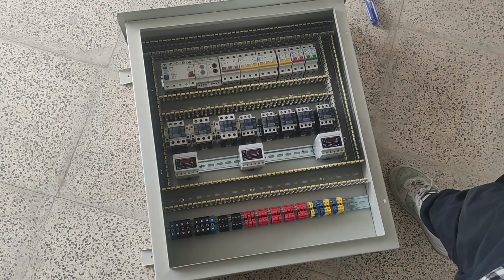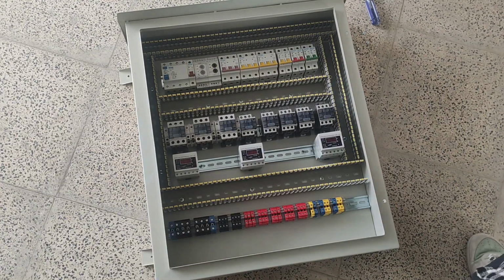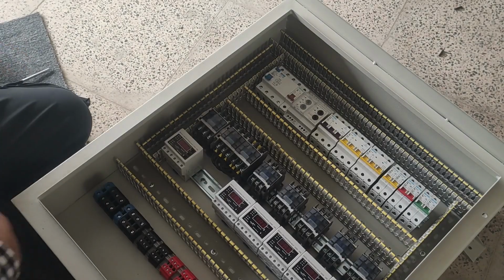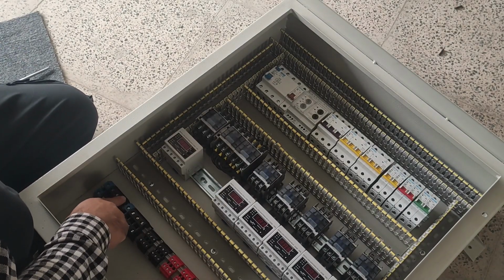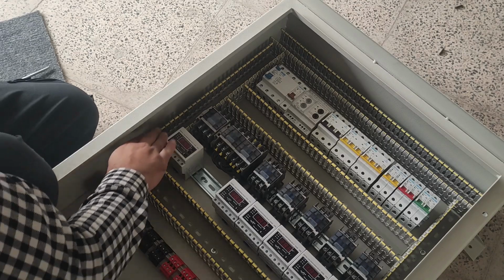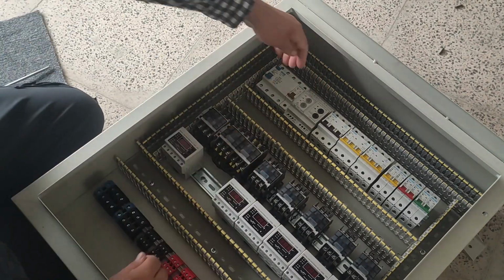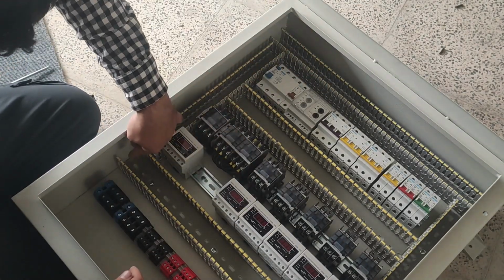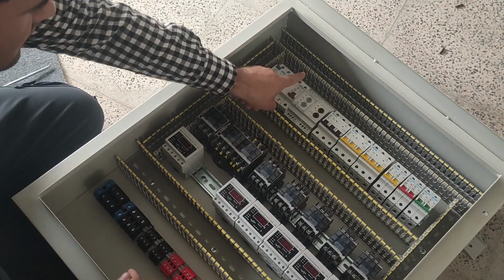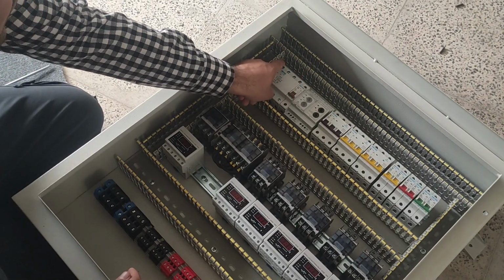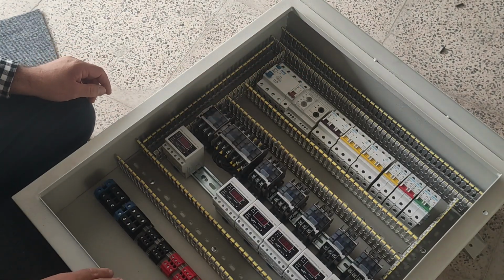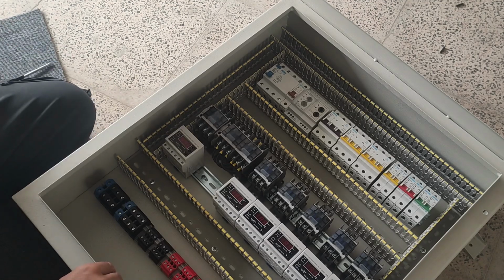The installation of equipment is finished. Now we start the wiring. At first, I connect the input three phases and neutral from the input terminals to the RCCB switch. By doing this, the three-phase power enters the main switch and is connected to the rest of the switchboard equipment.